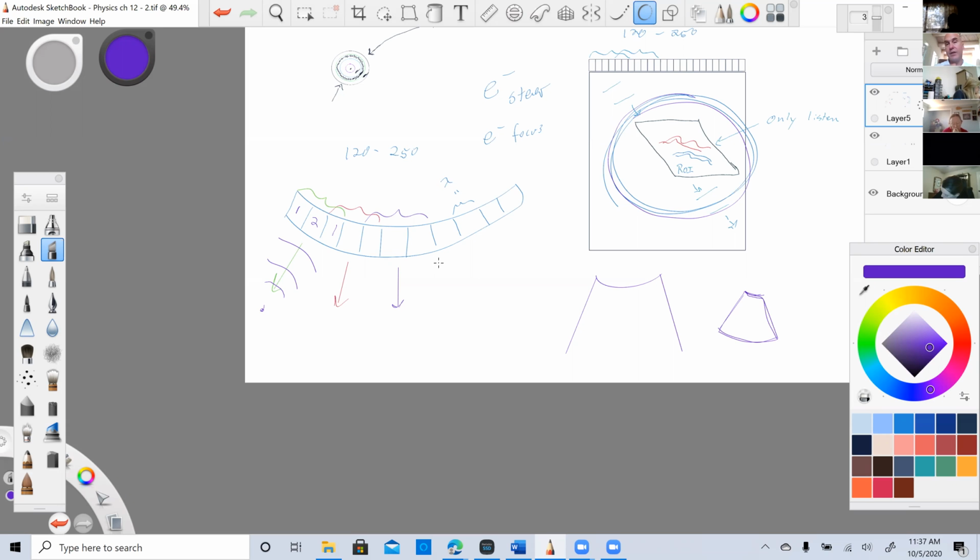There's no steering of the color box on the curved transducer. You can move the color box, and it's going to be shaped a little bit like that too, a bit of a rounded top. You can move it from side to side and up and down, but you cannot steer it. The beam lines creating that color box are still coming straight out of the transducer, even though it seems like it's curved.